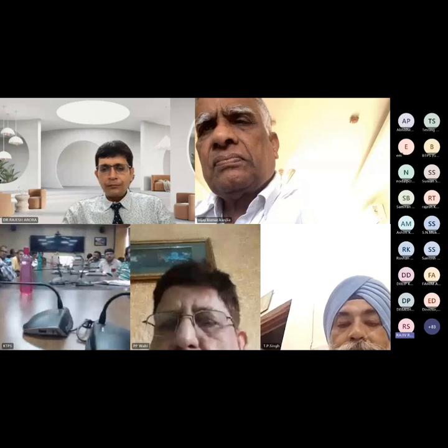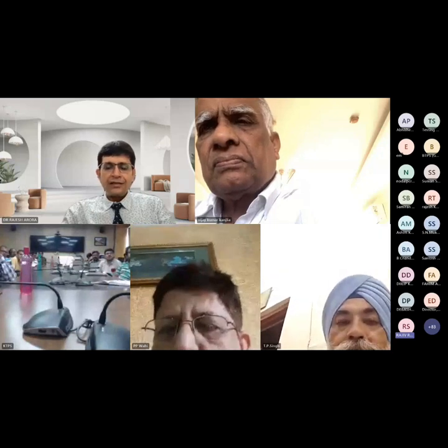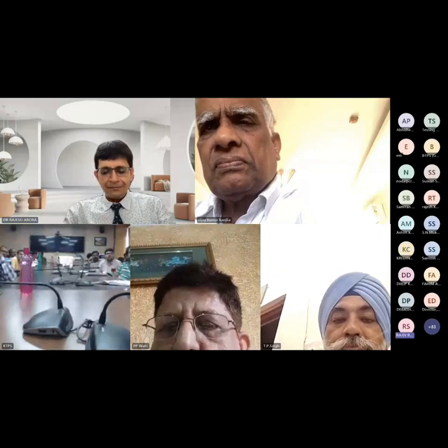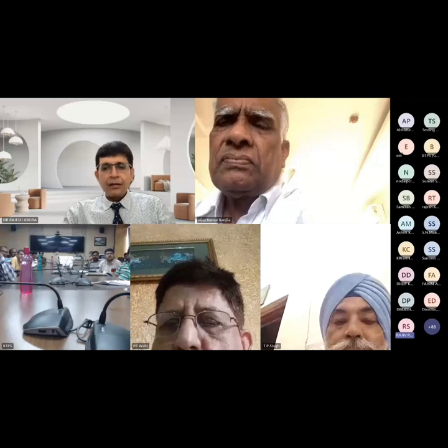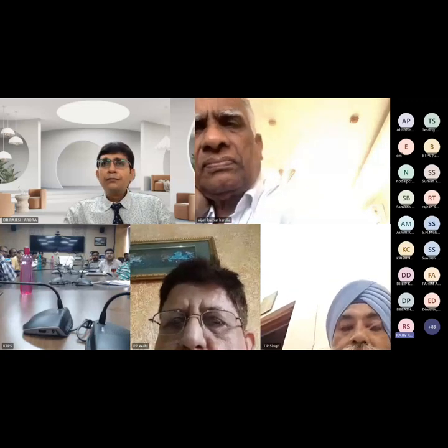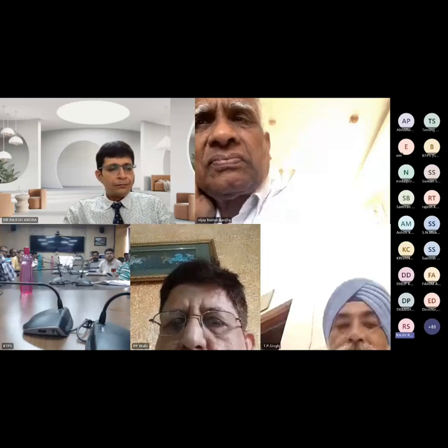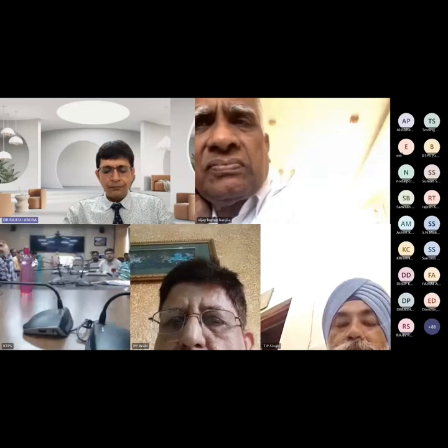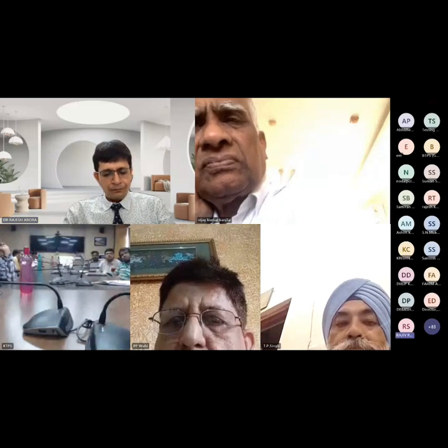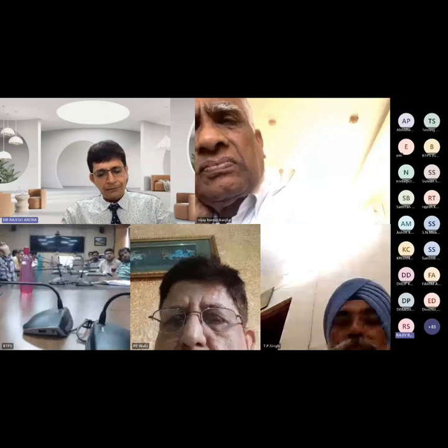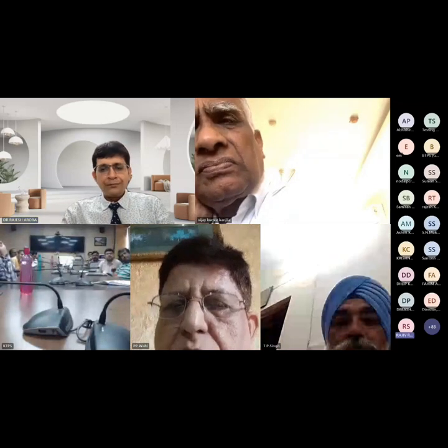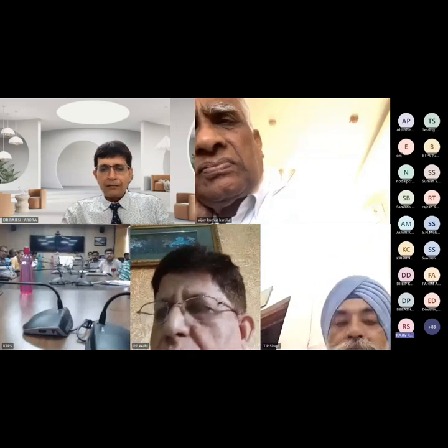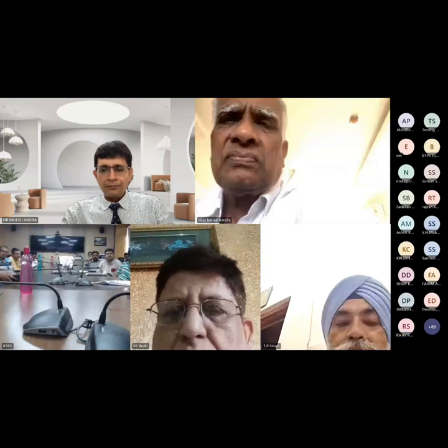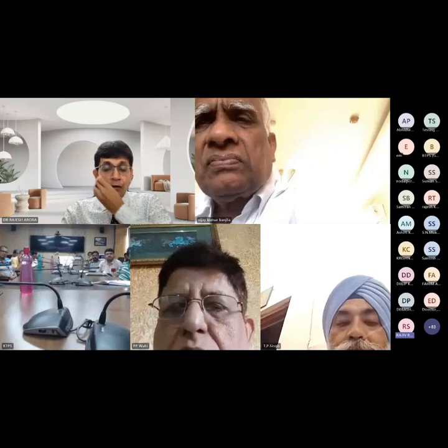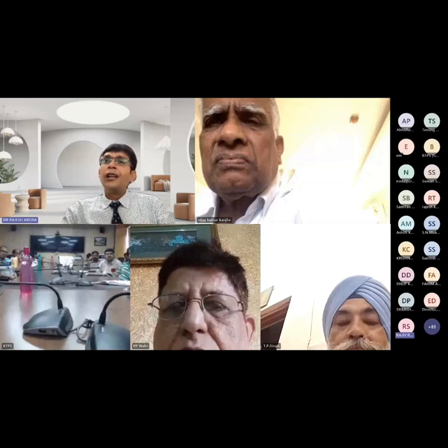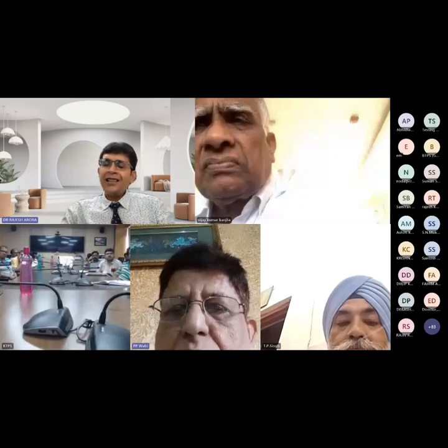So Rajiv Ranjan Sinha again, this side, sir. I have one query. Whether the lightning arrestor, that is, the lightning rod we install on the uppermost part of our building, as I came to know earlier, should be earthed separately and independently, away from the global grid? Yeah, it should be interconnected.